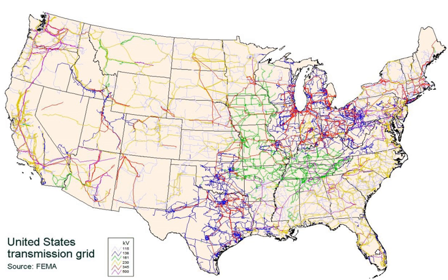Droop speed control is a control mode used for AC electrical power generators, whereby the power output of a generator reduces as the line frequency increases. It is commonly used as the speed control mode of the governor of a prime mover driving a synchronous generator connected to an electrical grid. It works by controlling the rate of power produced by the prime mover according to the grid frequency.